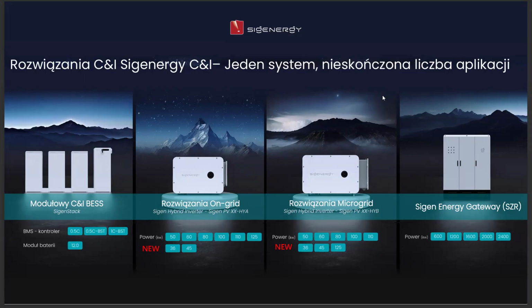In the inverter segment, we offer two solution types. Pure inverters. Hybrid inverters, without the need for external backup boxes. Our standard commercial power range covers 50 to 125 kilowatts. At the same time, we have also prepared something dedicated specifically to the Polish market, 36 kilowatts and 45 kilowatts inverters. Why is this so important? In Poland, many customers have grid connections in the 40 to 50 kilowatts range. Exceeding that threshold usually means higher contracted capacity charges, moving into a different tariff group, and often costly formal/technical procedures with the DSO. Using a 45 kilowatts inverter allows the system to fit perfectly within the existing grid connection, without paying for capacity the customer does not actually need.